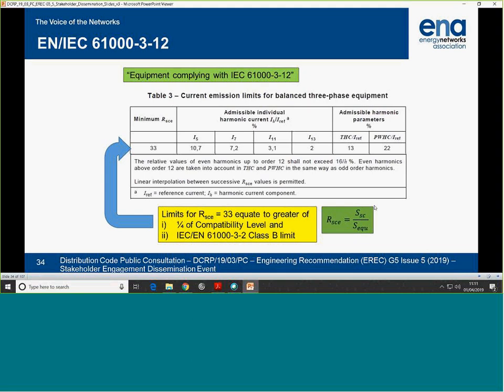Well, the 10.7% is actually derived from two things. It's the current that would give you a voltage of a quarter of the compatibility level, and it's also higher than the other. Over the two values, it's the value when you look at the 61000-3-2 standard for Class B products, which are portable tools, which get 150% of the rating of the Class A products, the higher two. So in that particular case, the compatibility level gave 9.9%, but with a factor for the portable tool aspect, it was rounded to 10.7. So that's where that comes from.